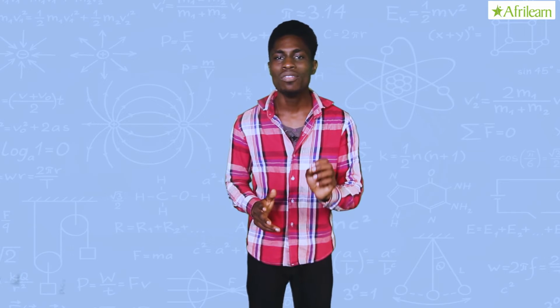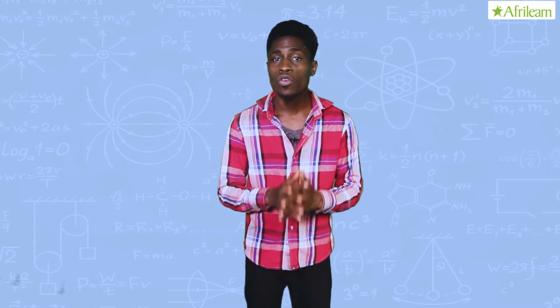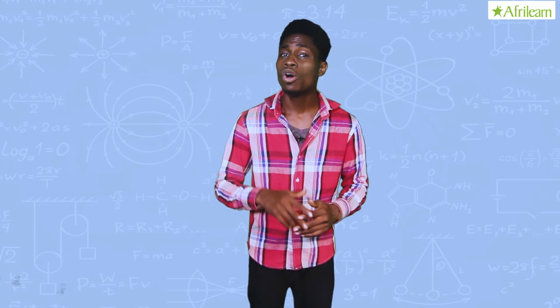Complete discharge is, however, likely to result in the disintegration of the electrode, so it is a standard practice to recharge lead cells before the open circuit voltage falls below 1.8 volts. Once the voltage becomes below 1.8, it becomes difficult to recharge the battery. Therefore, it should always be checked that this voltage does not fall below 1.8 volts.